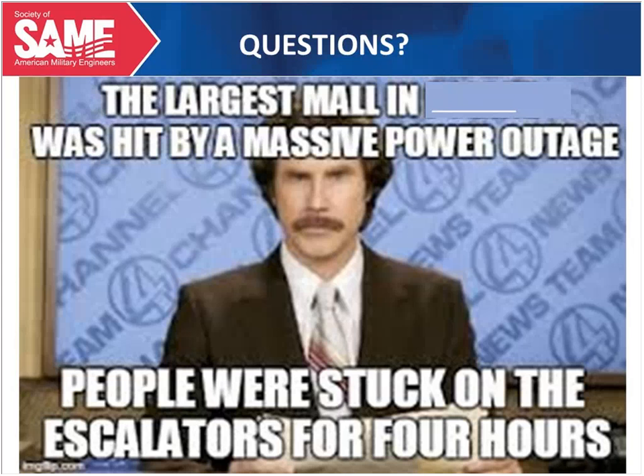In terms of energy security, I'd say pretty much the same strategy I outlined. It's going to be hard today — though this could be changing — to get away from a standard diesel genset as your workhorse or base load backup generator. That's changing, and there are absolutely some exceptions, but you treat that as step one, then augment with PV in some way, using controls for the PV. It's a pretty cost-effective way to do it, since the PV gives you benefits year-round. Almost all areas allow what's called net metering, so any excess the PV produces just goes onto the grid in the normal case, and if you lose grid power, you use the controls we talked about for syncing up the PV production and the generators.